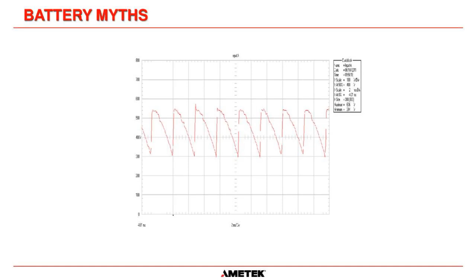So this is from the C&D manual, and this is an AC ripple voltage imposed on the DC charging voltage. And it's saying 0.9% peak-to-peak AC ripple. So this isn't bad ripple. Now, the important thing to mention here is this is the open circuit voltage of the battery. And what that means is if you took the battery off charge, that is the voltage that the battery will sit at for a prolonged period of time until it starts self-discharging, okay?